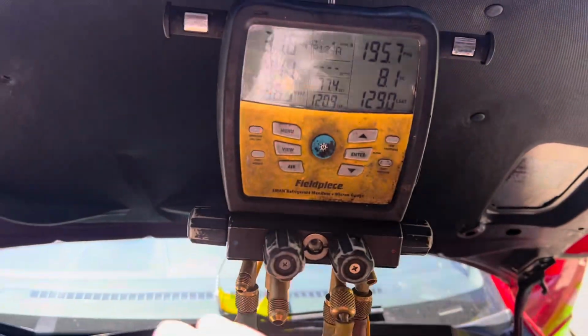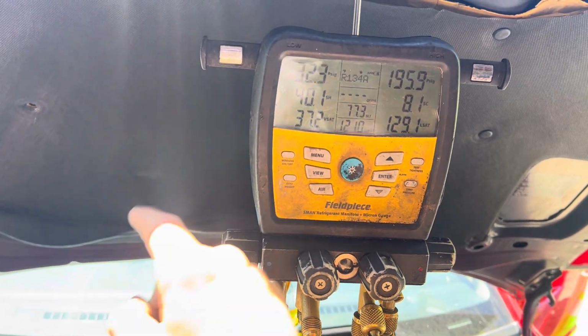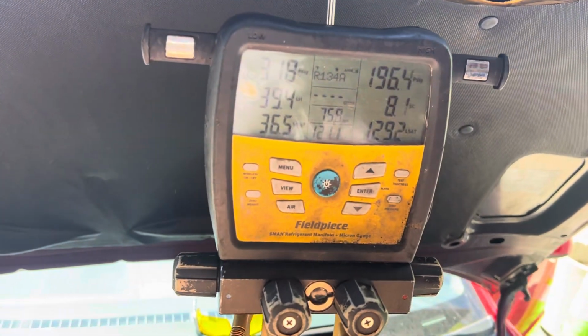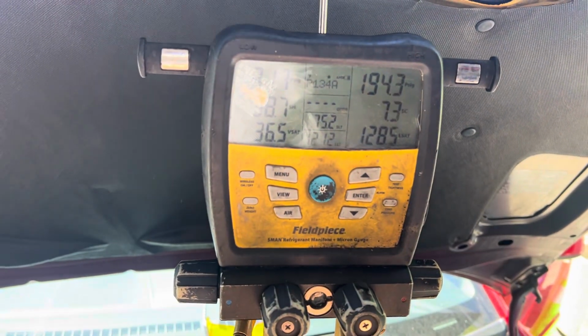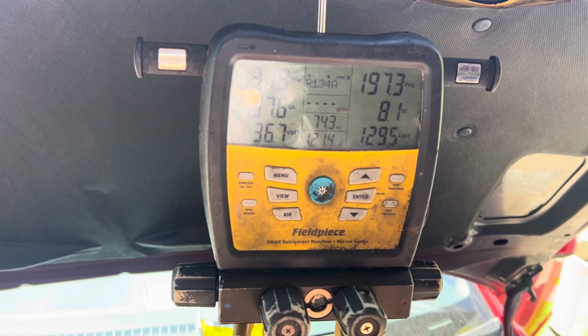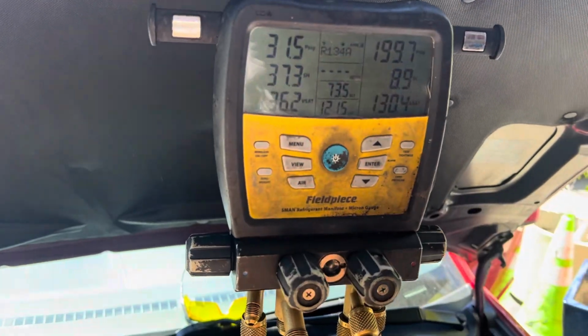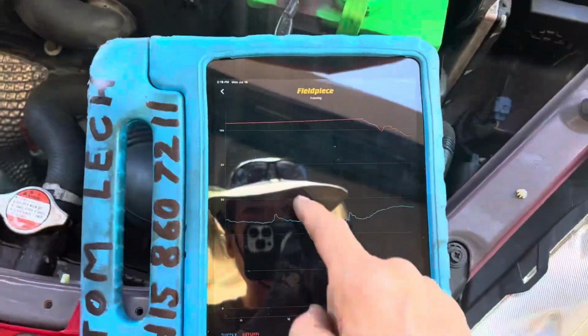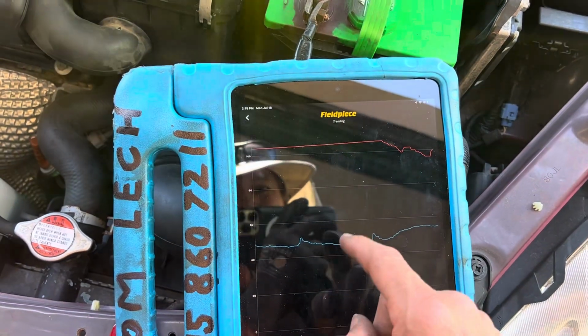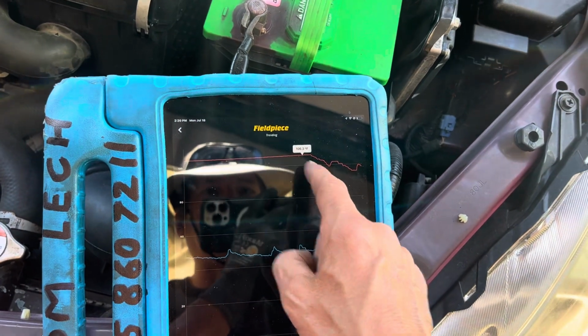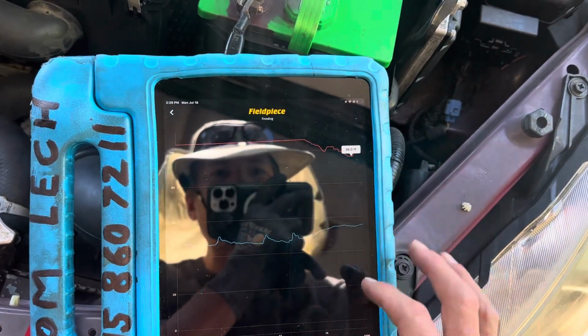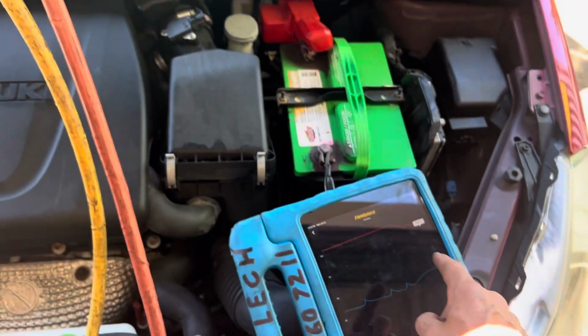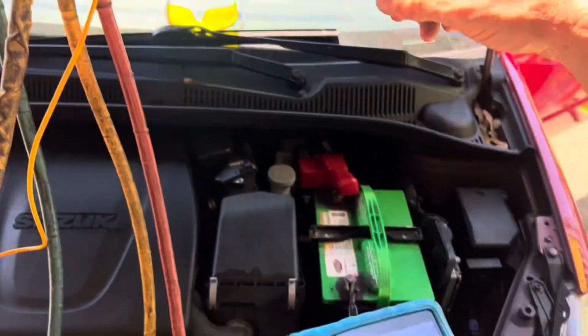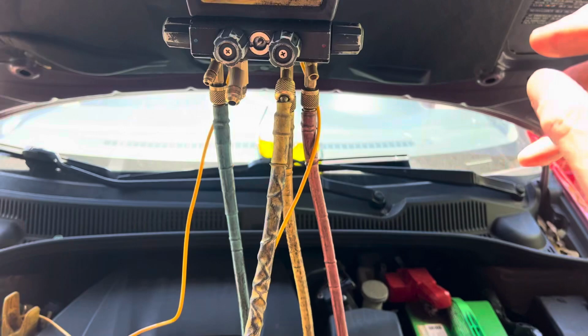And you can see our superheat went up, because we have more load going over the evaporator, and look at the superheat come down. It's trying to get there. And it's going down, as our compressor is stroking up, it is trying to compensate for that heavy load. What's our temperature? Oh, that's when it was off because it's just sitting there being saturated with hot air. 96 degrees. So we got 96 degree air going over the evaporator. So instead of recycled air in the 70s or so, we got almost 100 degree air going over the evaporator. There we go. It came back down to 37.